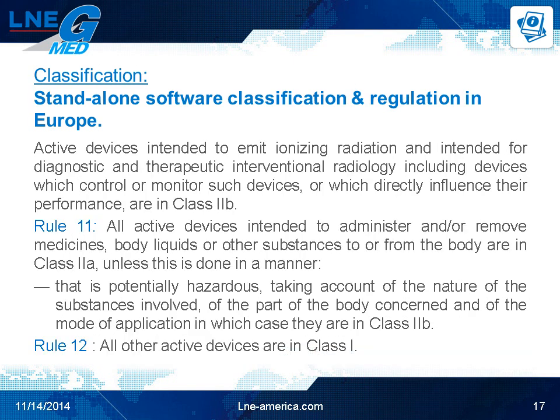Rule 11 states that all active devices intended to administer and/or remove medicines, body liquids, or other substances to or from the body are in Class 2A, unless this is done in a potentially hazardous manner taking account of the nature of the substances involved, the part of the body concerned, and the mode of application, in which case they are Class 2B. Standalone software that drives such medical devices or influences the use of such a device — for example by calculation — falls automatically into the same class as the device it drives, according to implementing rule 2.3. Apps on a cell phone to calculate and recommend an insulin dose before injection are considered Class 2B, even if the software is not directly connected with the injector.